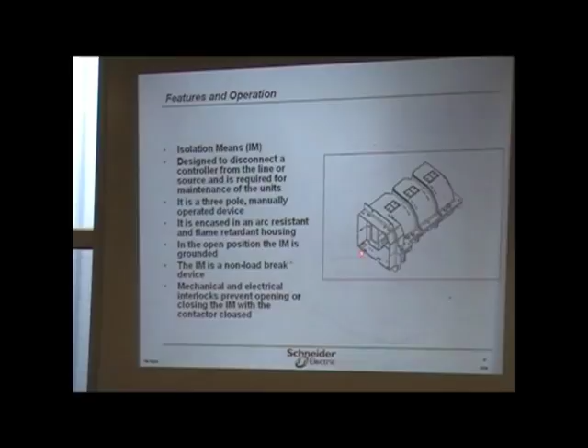So that's why, if the contactor is de-energized, in essence it's just like a regular contactor that has a coil. The coil energizes the contactor that closes the actual contacts. Okay, so essentially what this isolating means is, the contactor coil has to be de-energized before you're able to open this isolating means, which is just a switch, in other words, in line with those contactor coils or the contacts themselves. So if you can just imagine this being a switch, and then you've got coils or contacts in series with it. So the contacts would energize or de-energize. It has to be open, so it's a non-load device, and that's how it comes into play.